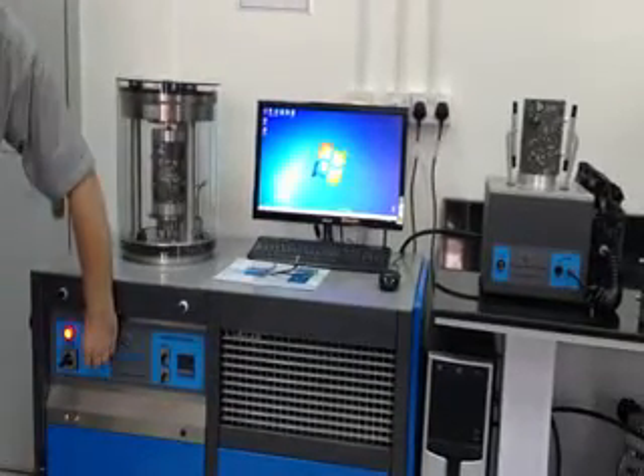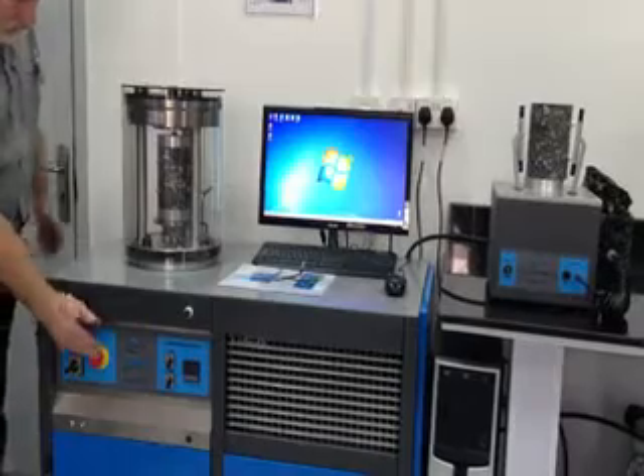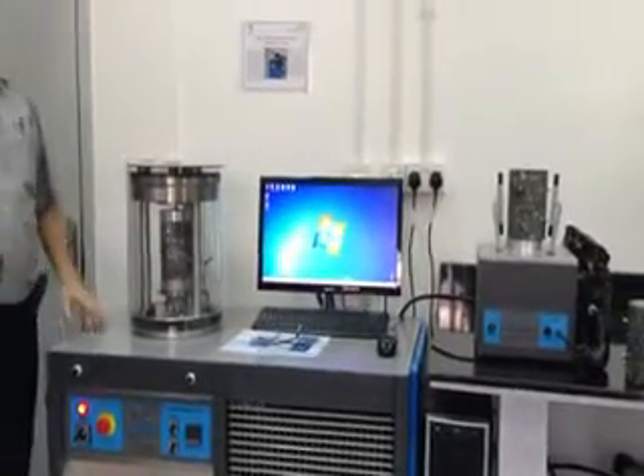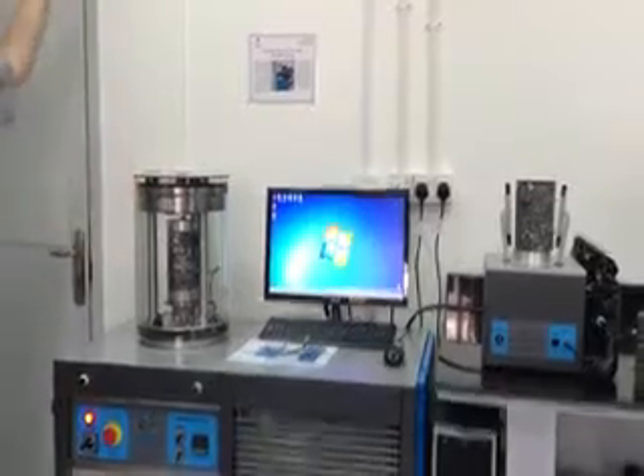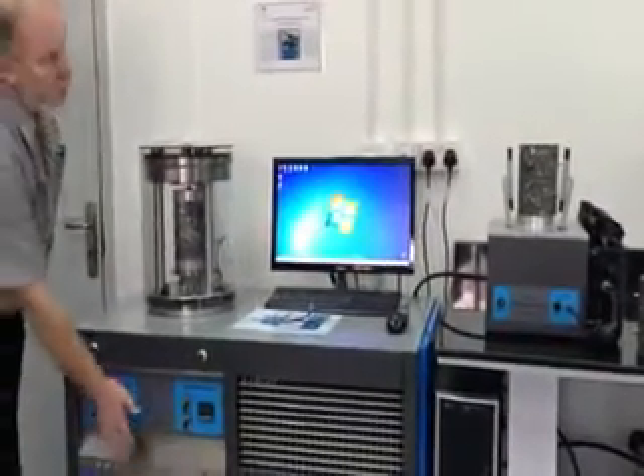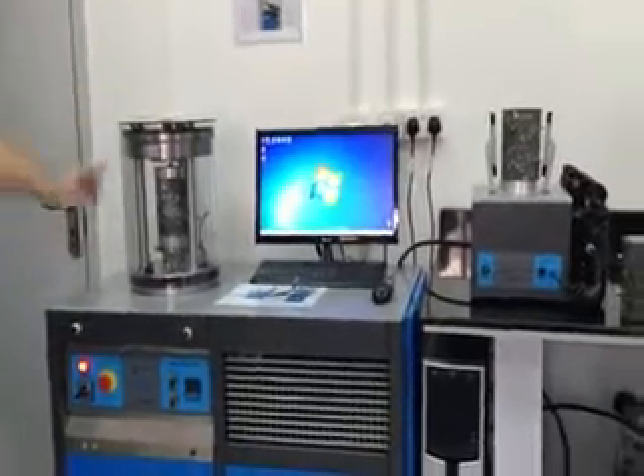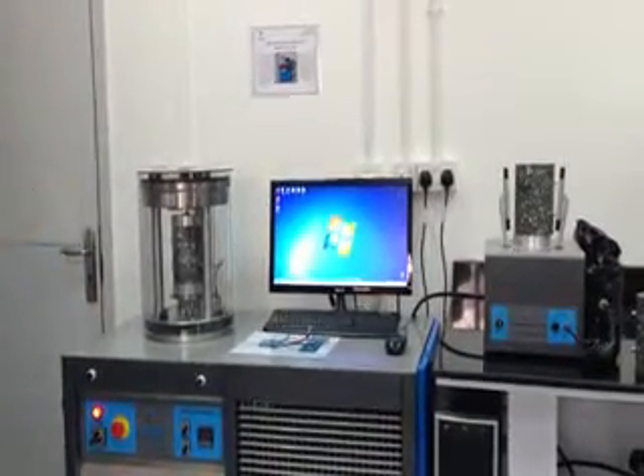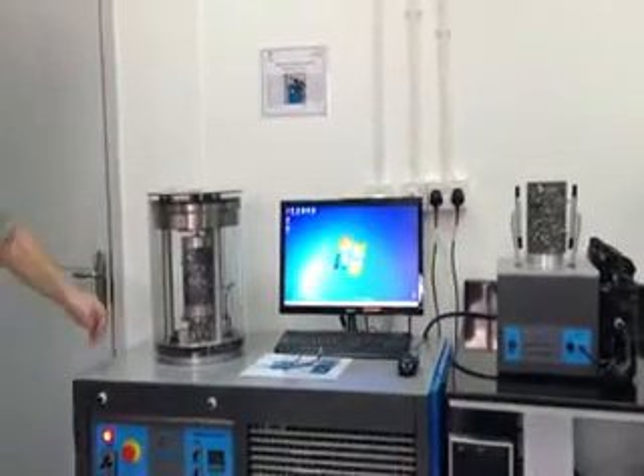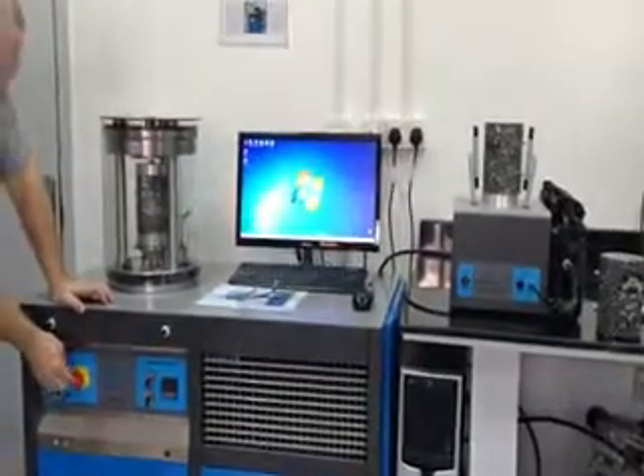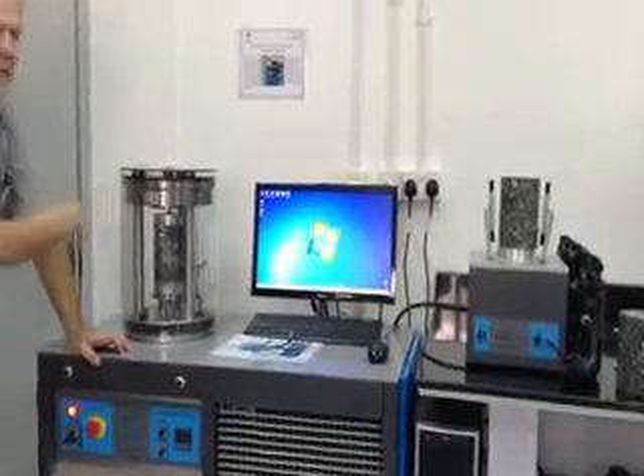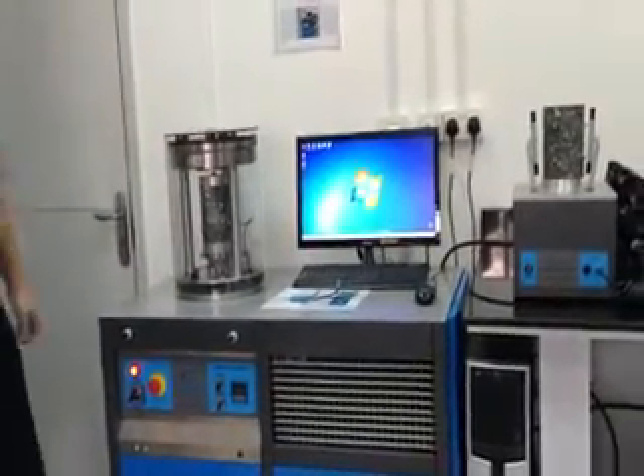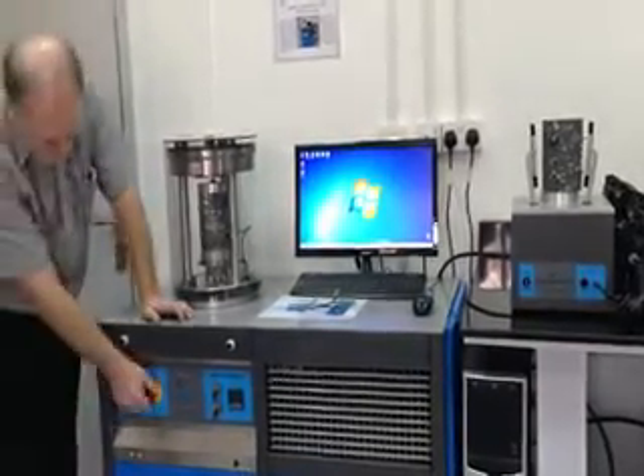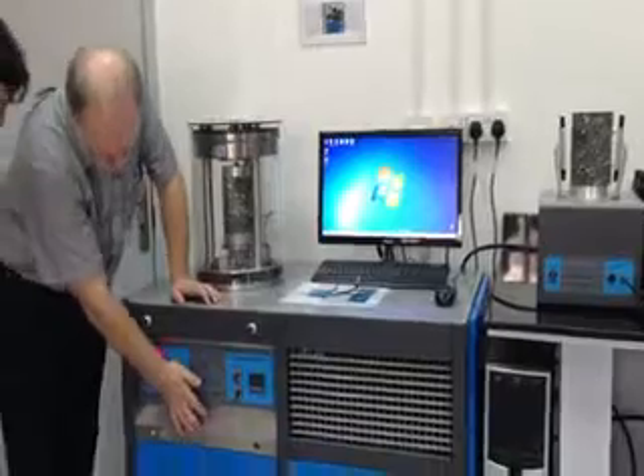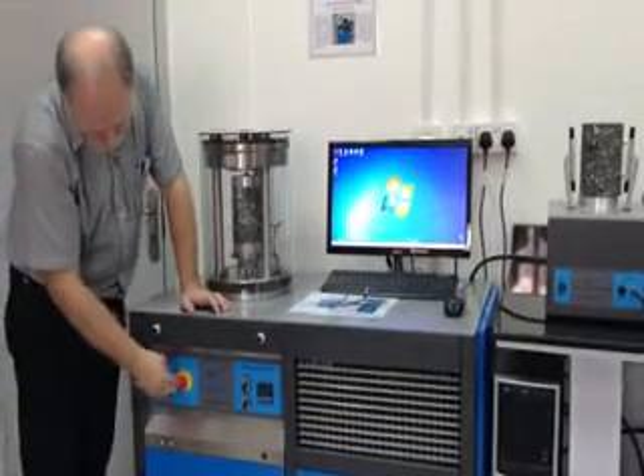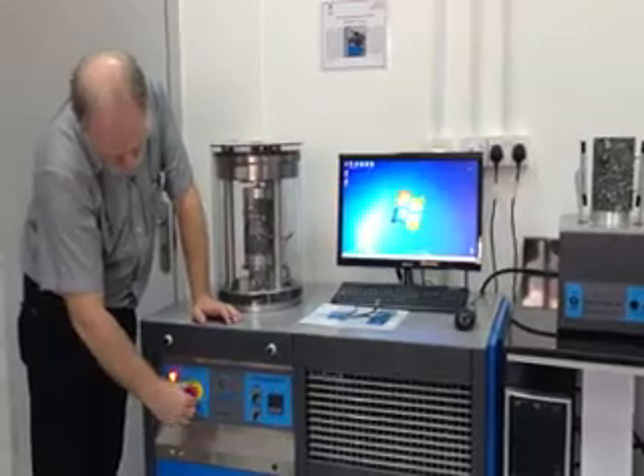This is an emergency stop button, so normally if it's pressed in, it isolates the external air pressure. So if for some reason something fails and the full pressure from the air supply tries to come into the system, that will stop it and lock it. The same thing, if the power goes off, there's a solenoid in there which will lock out the air supply. So you shouldn't damage your sample if something happens. So when we get to the software later, you'll see if this is activated, pushed in, you can't run the test because it disables some of the functions. So it's always pushed out when it's open. Yeah. So it's closed. Yeah. Closes in. To open it, you turn it, and it pops out.